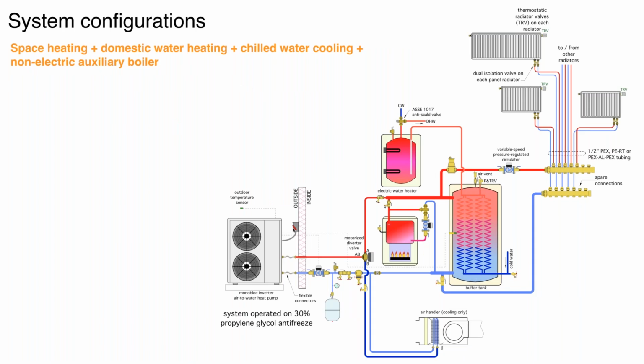Okay. Same system, the only difference being now a fossil fuel boiler. This could be natural gas, propane, fuel oil. Very important detail. If we're going to operate this system at low water temperatures, if we're using outdoor reset control, or maybe we're adding insulation to the building to bring down the supply water temperature, or maybe we're adding heat emitters to also bring down supply water temperature.